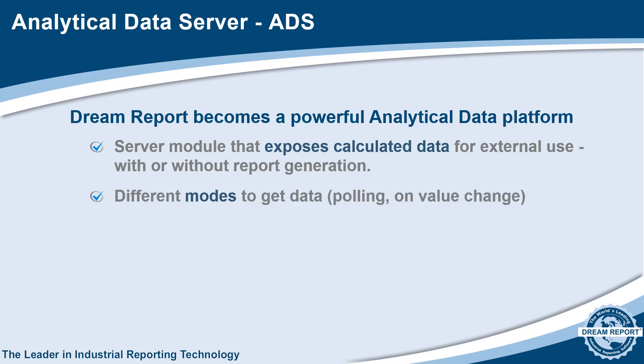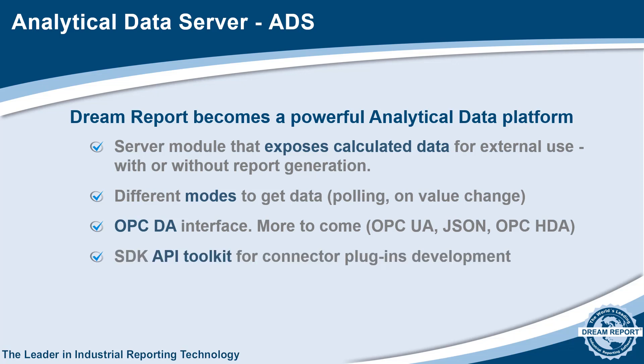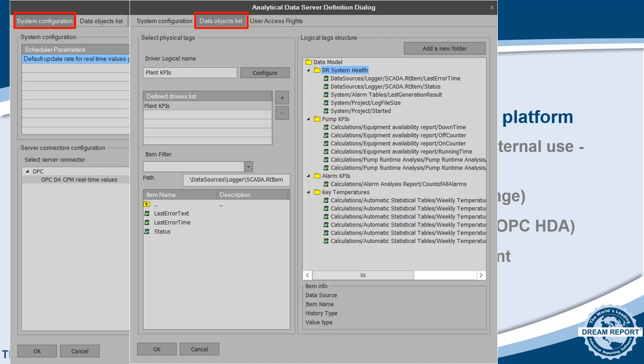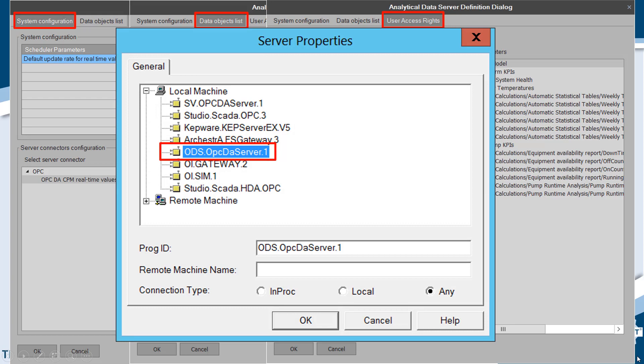External applications can get the data as needed, whether polled or on value change. In this release, the data is exposed through a new DreamReport OPC DA server, with other OPC and JSON interfaces coming next, and an SDK API toolkit will be available for development of other connectivity plugins. Here we see the configuration of the analytical data server. Step 1 is to add the ADS instance to the project. Next, you add a logical grouping of items from the project that you want to expose through the ADS. Just like when configuring data models, you can create folders and drag and drop items from the project into the appropriate folders. You can even alias or rename the items to simplify the OPC browsing, and you can choose to have secured access to the exposed data items. Here we see the DreamReport OPC server exposed through a generic OPC client tool.